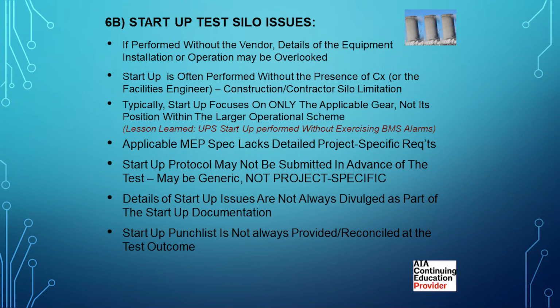The issue is that if you don't have that third person there, things can be overlooked. Sometimes startup is actually done by the contractor. If he's familiar enough with the gear, the vendor doesn't necessarily come out to look at some things. It depends on the complexity of the gear, it depends on the project. But if somebody says, hey, I've worked with UPSs all the time, I don't have to have Liebert come out and check something, if that's part of how they're going to try to save time and effort, the problem is that's not the SME you want to have there. So who comes out and does the work matters, and what they're going to be doing.